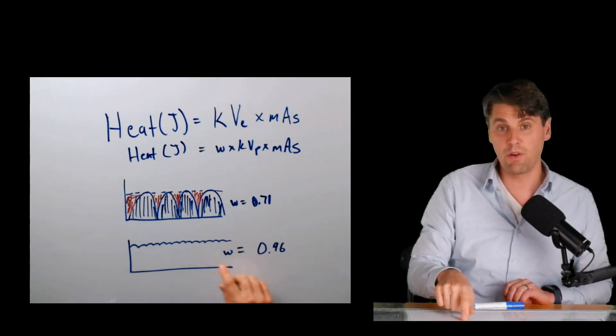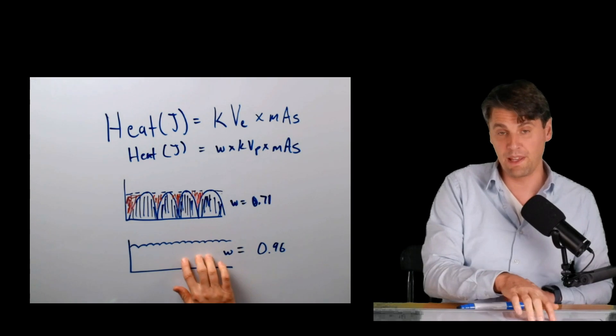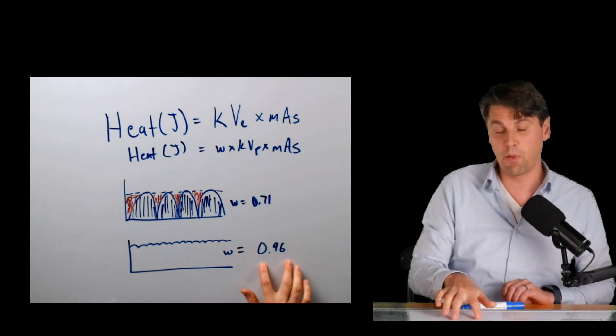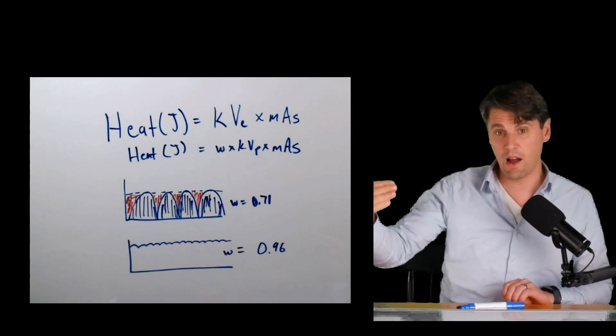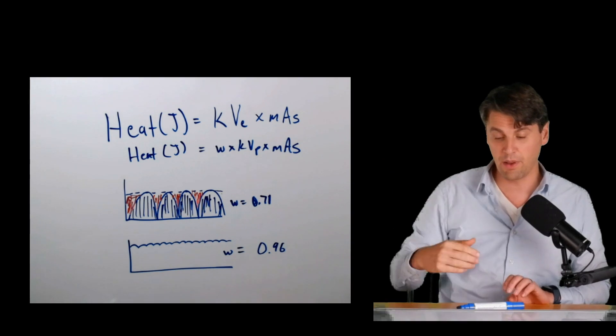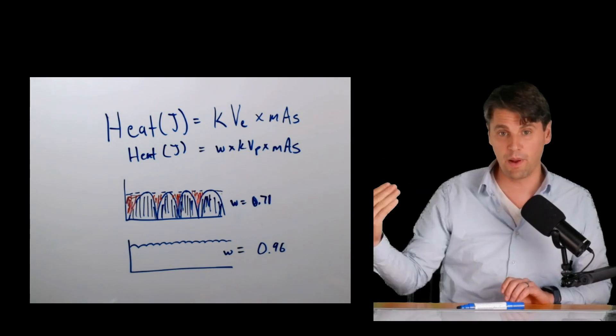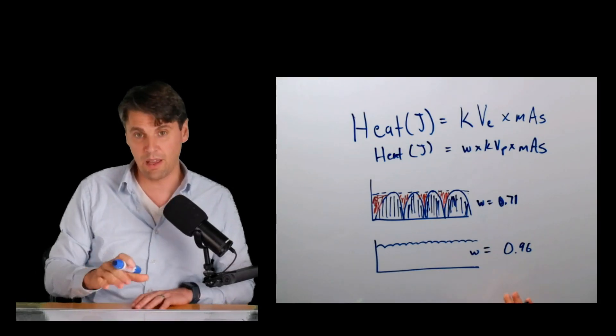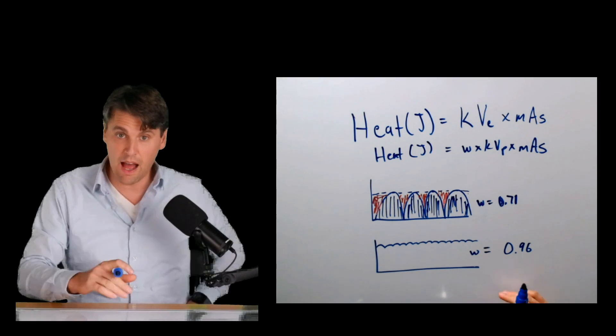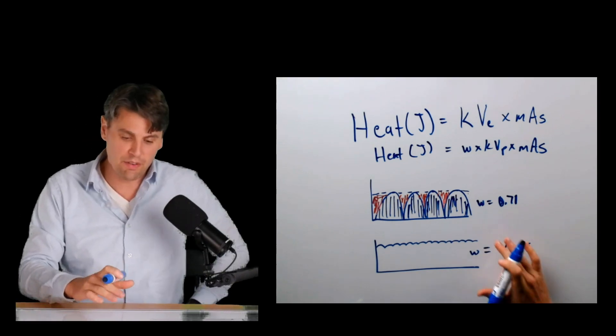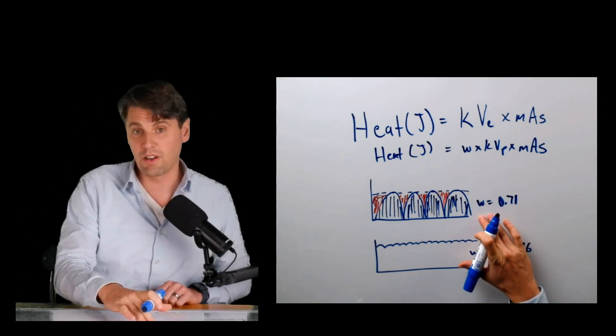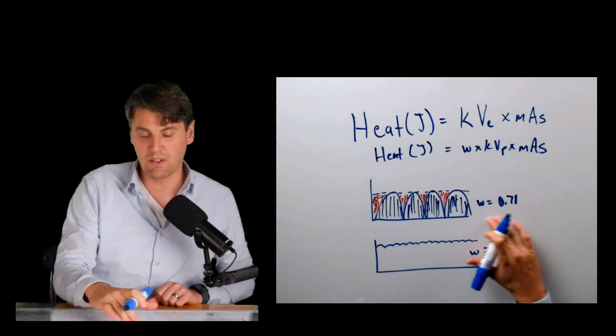For a three-phase system, W is 0.96. For a 12-pulse system, W is all the way up to 0.99. For a modern generator, W is typically pretty high in comparison with the traditional full wave rectification circuit, which was 0.71.